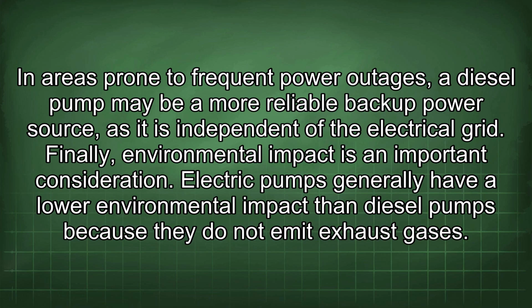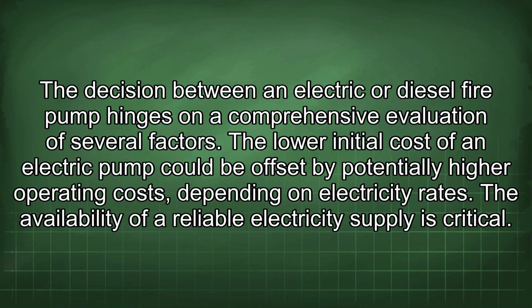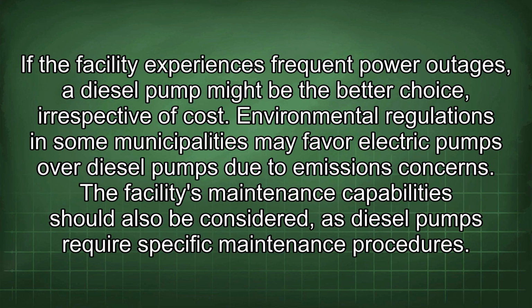Finally, environmental impact is an important consideration. Electric pumps generally have a lower environmental impact than diesel pumps because they do not emit exhaust gases. The decision between an electric or diesel fire pump hinges on a comprehensive evaluation of several factors. The lower initial cost of an electric pump could be offset by potentially higher operating costs depending on electricity rates. The availability of a reliable electricity supply is critical. If the facility experiences frequent power outages, a diesel pump might be the better choice, irrespective of cost.